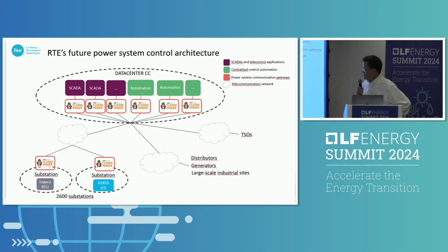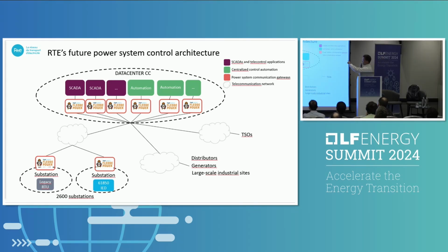So this is their graph. What they actually have is, I think, for every 150 substations, they have a FLEDGE, and then each one of those gets aggregated. So you have 150 substations connected to the RTUs, 150 FledgePOWERs that then aggregate to a single FledgePOWER that then goes to their SCADA and their automation data center. And that's basically the new architecture. Now they've deployed so far in 8 substations. And the plan is, and you should probably ask them, to have about 600 done by next year.